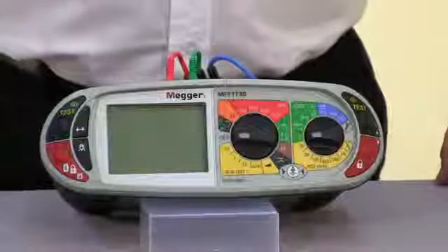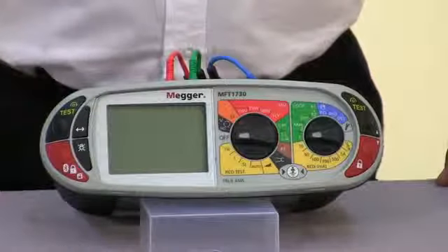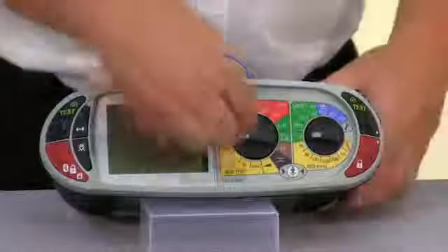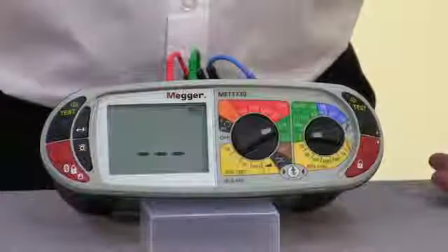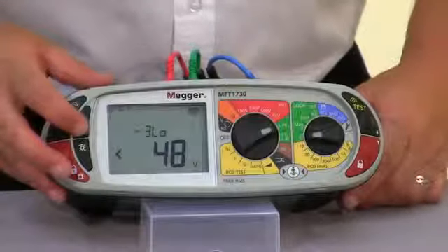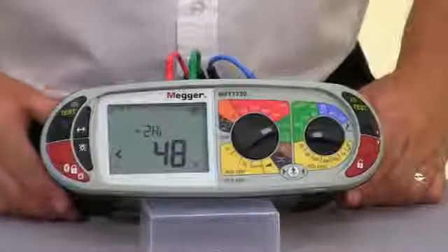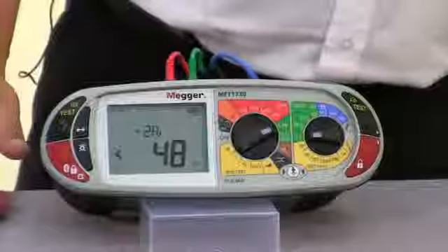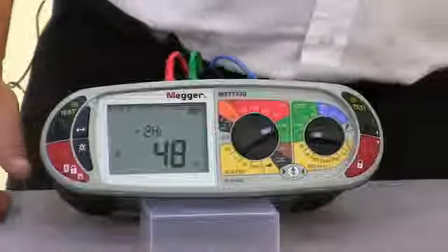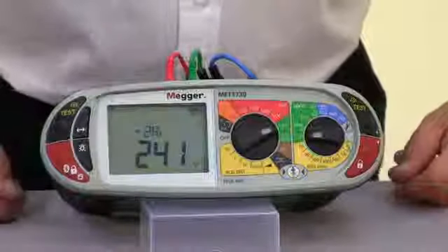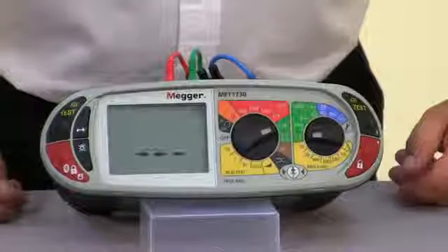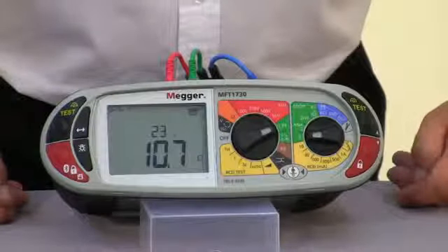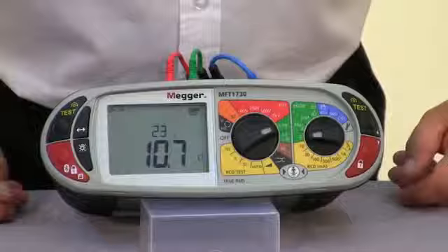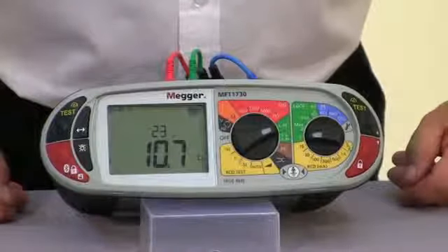The final earth loop test we'll look at will be the straightforward 2-wire high current test. So selecting our LPE and our Z measurement, using the function key we can select our 2-wire high current test, plugging the unit in. Again, auto start, and the reading 10.7 ohms and 23 amps PFC.